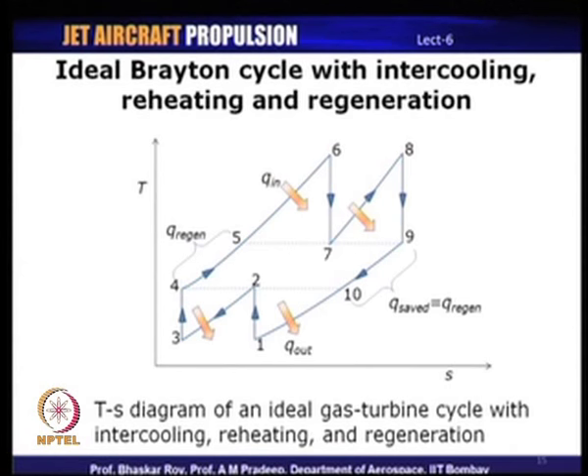While thermodynamically it is straightforward to implement inter cooling, reheating, and regeneration, there are practical limitations. Increasing the number of compression or expansion stages substantially increases mechanical complexity, weight, and cost. Normally, two to three stages of inter cooling and reheat is the maximum that is economically viable in practice.